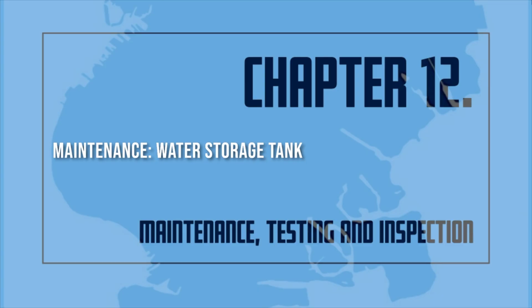C. Water storage tank. Water level. The tank shall be maintained full or at the designed water level. Drain silt. Silt shall be removed during interior inspection, semi-annually, or more frequently as needed to avoid accumulation to the level of the tank outlet. ESCF, embankment-supported coated fabric suction tanks. The maintenance of ESCF tanks shall be done according to the tank manufacturer manual.